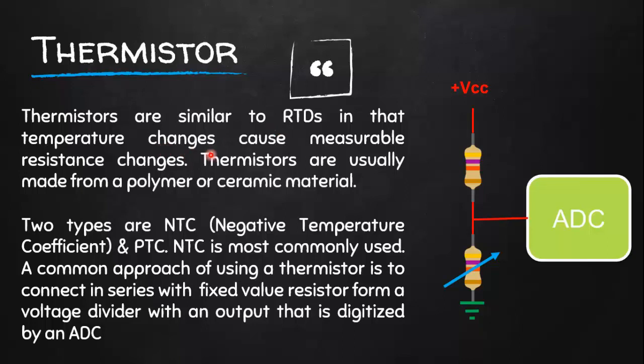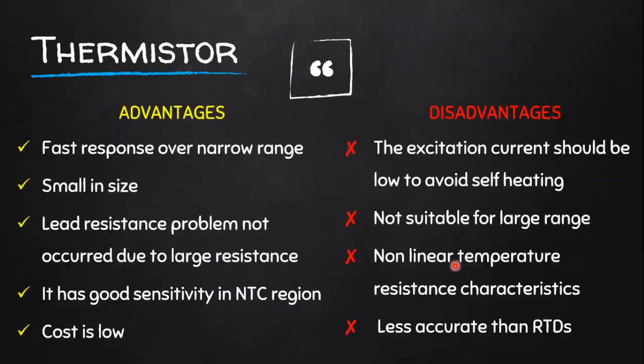Next come thermistors. Thermistors are very similar to RTDs because their resistance also changes with temperature. Thermistors are usually made from a polymer or ceramic material. There are two types: NTC, which is Negative Temperature Coefficient, meaning resistance decreases with increasing temperature, and PTC, Positive Temperature Coefficient. NTC is the most commonly used. A common approach is to connect an NTC in series with a known resistor to make a voltage divider circuit, so as temperature changes, the resistance of the NTC changes and we can measure the voltage at the common point.